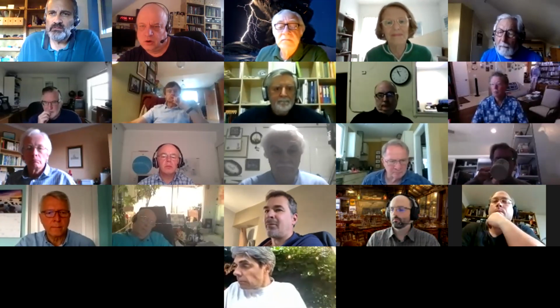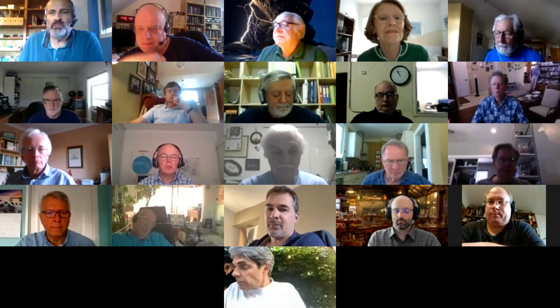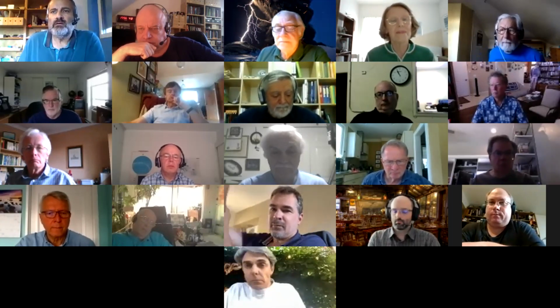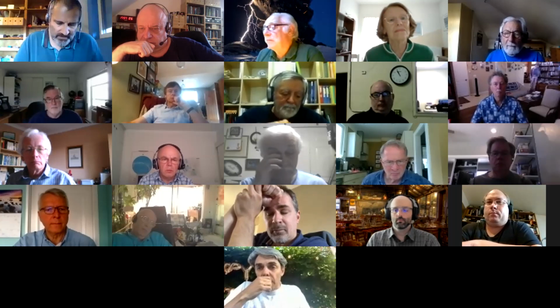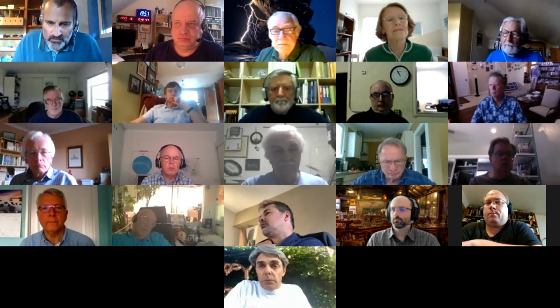Okay. Well, Olivier, I will not read all the questions. Or no, there's something. Maybe I see a question from Christine here. Could you explain why you have to do a calibration spectrum for each observation? In fact, this is not really for each observation, but at least for the ALPY, this is at least one time during the night. It depends on the calibration precision you need in your case. But for sure, as long as you do not change anything in your instrument, the calibration dispersion with the calibration spectrum will never change. So you can keep it for a long time.